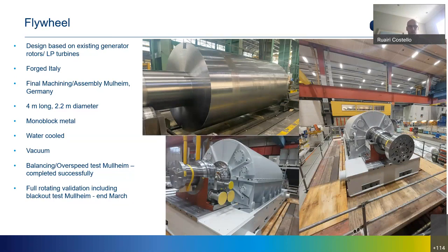The design is based on existing generator rotors and LP turbines. The forging was carried out in Italy. That's the top picture there. You can actually see a sample taken from the end of the flywheel, and that would have been machined out when it was delivered to Mülheim. It's 4 meters long, and it's 2.2 meters in diameter, and it's just one block of metal. It's water cooled, and it's under vacuum to reduce friction losses.